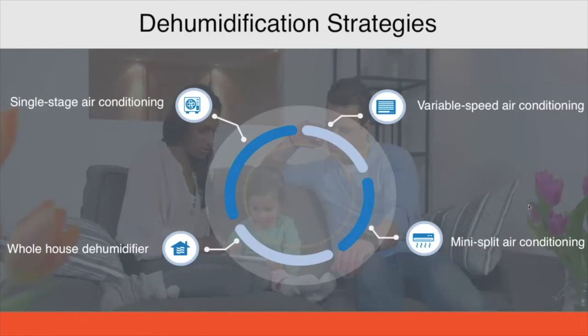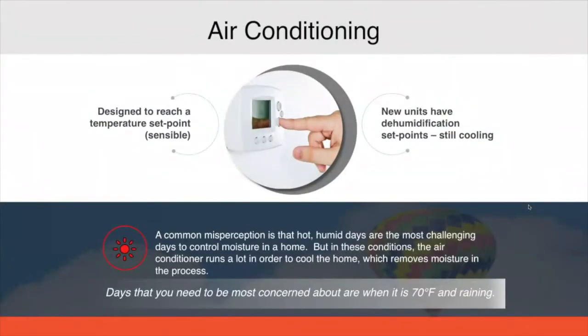So our dehumidification strategies: we have single stage air conditioning, variable speed, mini split, and then the whole house dehumidifier. And we're going to discuss the challenges with that from the AC side. Again, air conditioning is designed to reach a temperature set point. It's based on sensible. Now they do have dehumidification options. Most of the time, if it's not reheat, which very few of them typically are, it is overcooling to dehumidify. So it will be running longer, most likely at slower fan speeds to remove more moisture. So again, overcooling to dehumidify, and this does not address 70 and raining.